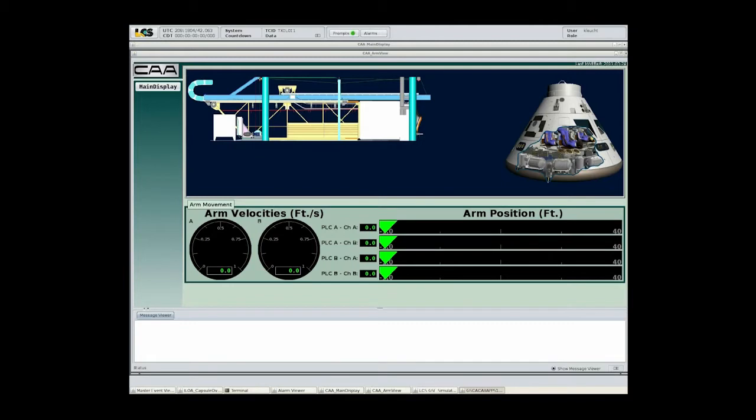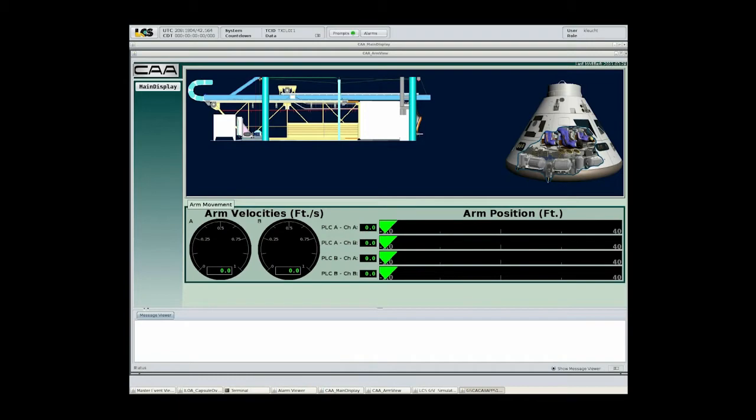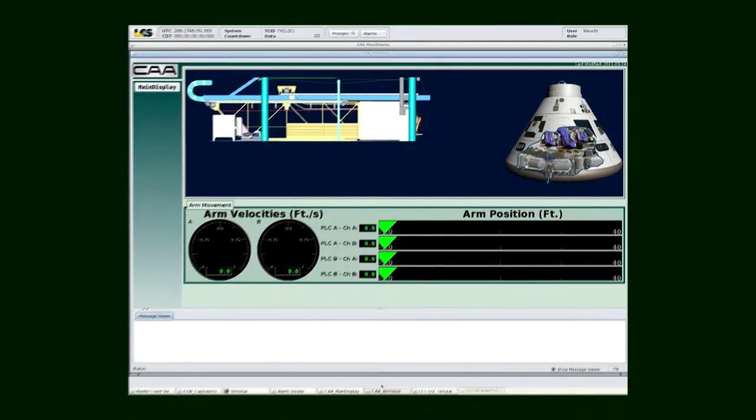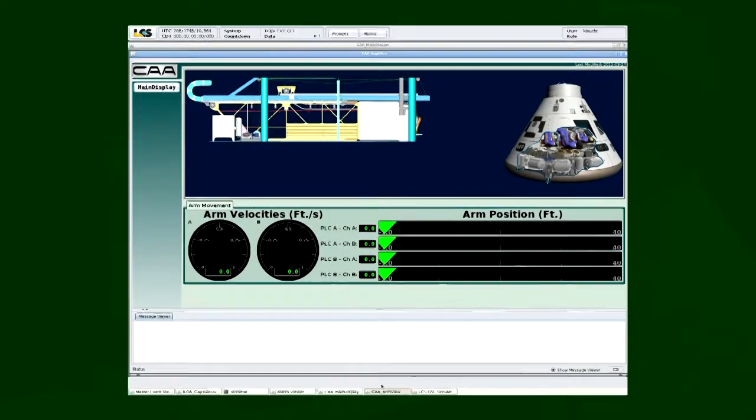As you will notice, we have multiple indications for the arm's position. Again, because this is a critical system, we also have multiple end items that are monitoring the system, and during emergency operations, we can actually monitor those items, determine if we have a failure, and operate in a reduced status even with a failed sensor.